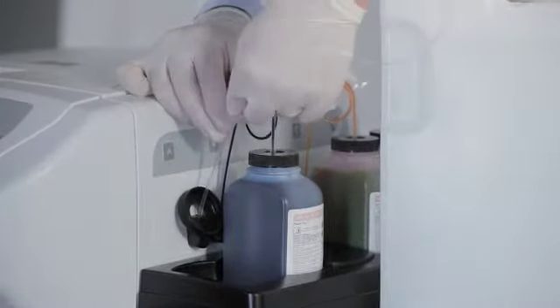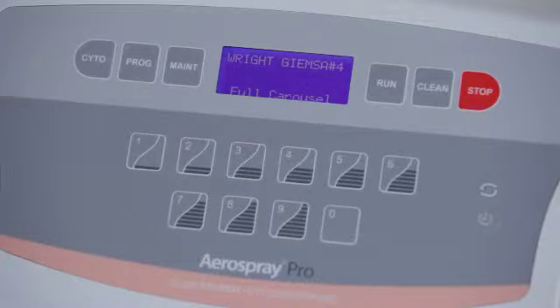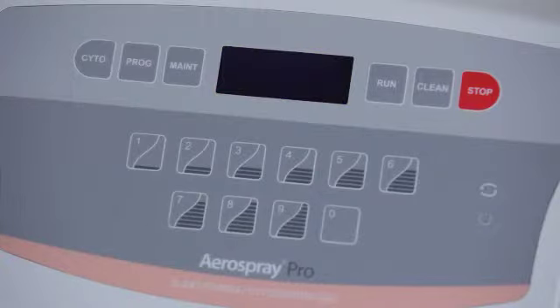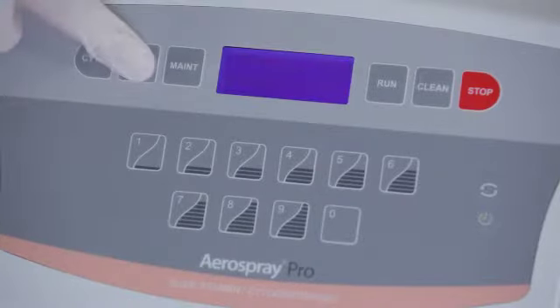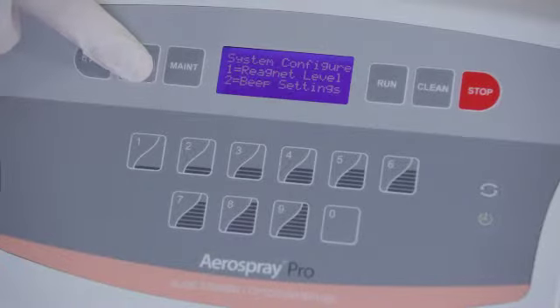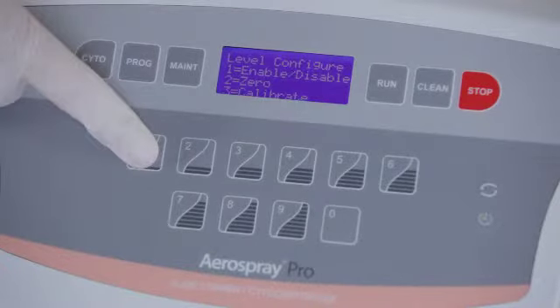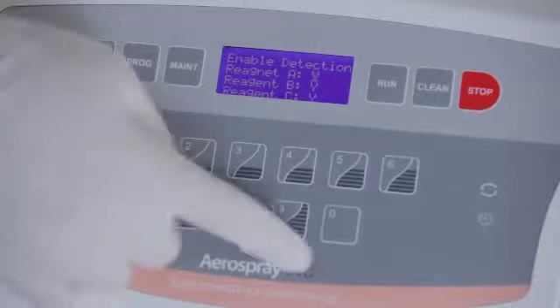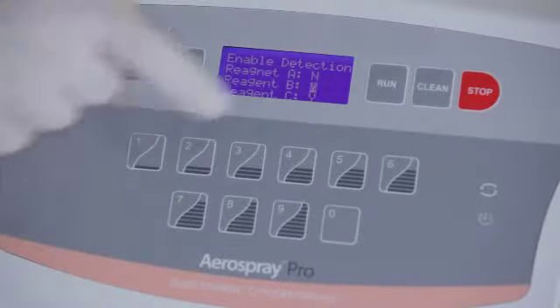After the 5-liter container is installed, the level detection feature for the A line should be disabled. It is disabled by turning the stainer off, then on again. Press Prog while the stainer is booting up. Press 1 for Level Sense. Press 1 for Enable Disable, then press 0 for Line A. This will deactivate the level detection for the A line.